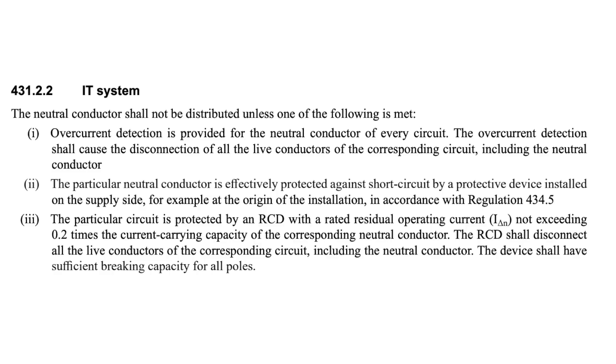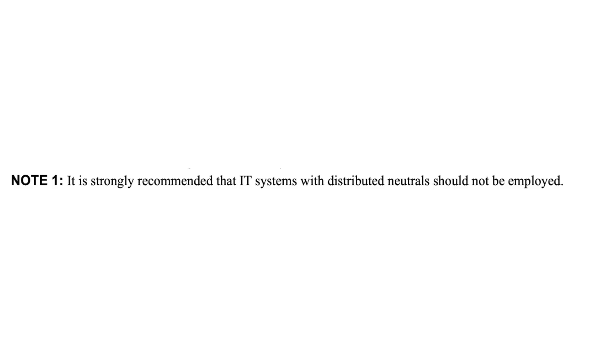The next regulation is 431.2.2, which relates to IT systems and says the neutral conductor shall not be distributed unless one of the following is met: first, overcurrent detection is provided for the neutral conductor of every circuit, and the overcurrent detection shall cause the disconnection of all the live conductors of the corresponding circuit including the neutral; second, the particular neutral is effectively protected against short circuit by a protective device on the supply side; or third, the particular circuit is protected by an RCD with a rated residual operating current I-delta-N not exceeding 0.2 times the current carrying capacity of the corresponding neutral conductor. So an IT system is another example of where we would need to consider protecting the neutral conductor. However, in Regulation 411.6.1 there is a note that says it is strongly recommended that IT systems with distributed neutrals should not be employed.